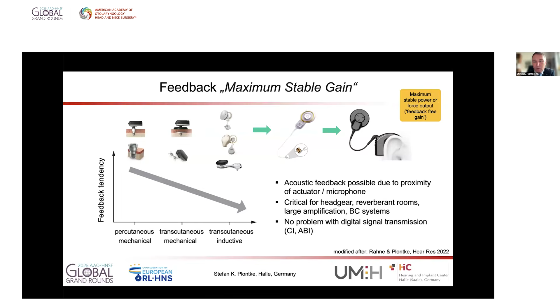So what is the feedback-free gain? Acoustic feedback possibly occurs due to the proximity of the actuator to the microphone. And this is critical for headgear, for instance, or in reverberant rooms, for large amplifications, meaning for very poor bone conduction thresholds. And it's, of course, worst for the bone conduction system. It's not a problem with a digital signal transmission system like a cochlear implant. So here we have a reduction from percutaneous through transcutaneous devices. It's not so much a problem for the active middle ear implants, and again, no problem for the cochlear implant.